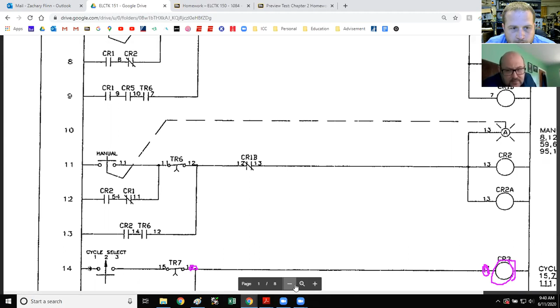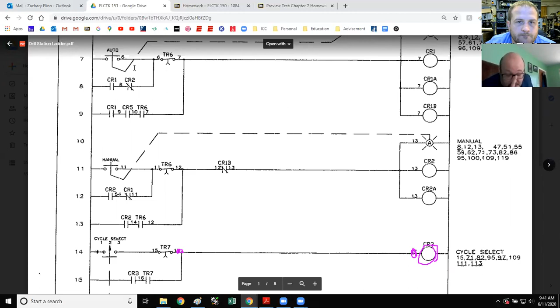So right here, okay, rung 8, in the key, rung 8 is underlined, so there would be normally closed on rung 8. CR2 normally closed. Okay, so these numbers you're talking about. Go ahead. The footnotes or side notes, they're underlined. Right, okay, yeah. So these numbers over here would be all the contacts elsewhere in the ladder diagram that these coils are controlling. Okay, all right, I understand now.